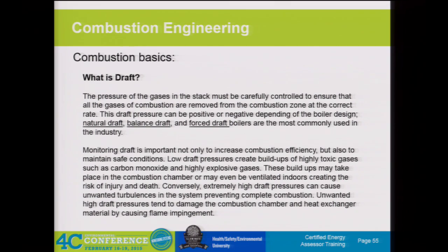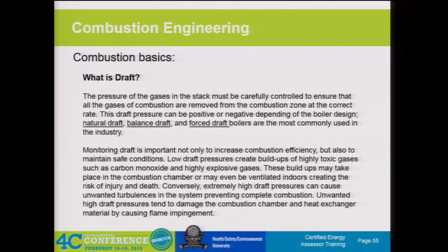Draft and leaks is mainly a problem when you've got fan systems in place. A lot of these systems have monitoring—most boilers have pressure on your fans, and pressure in different components of the air delivery system. The pressure at the exit to the firebox is also a very critical point. Usually about a half inch of water is a good operating range for negative pressure at the exit of a firebox. This is kind of where the engineering specifications in the energy assessment come into play. A lot of that is set up in the original design. If the fan's been replaced at some point and wasn't replaced with a like-kind unit or had different static pressure characteristics, that could affect things—so some of that history comes into play when looking at an energy assessment.